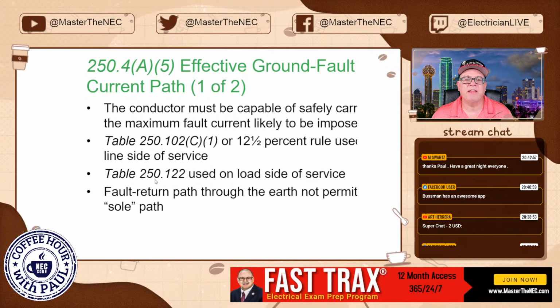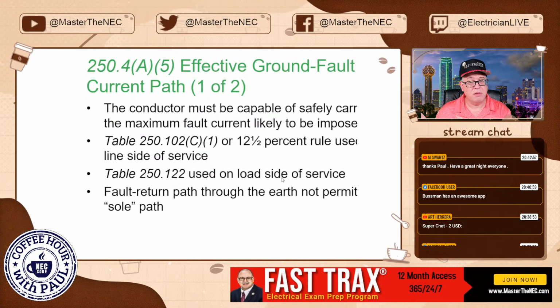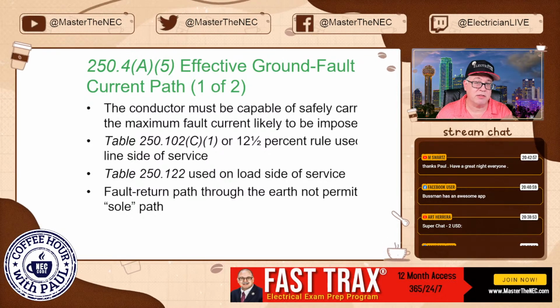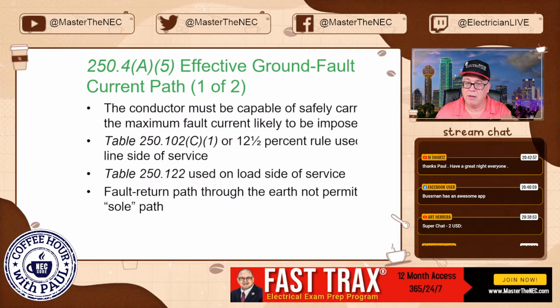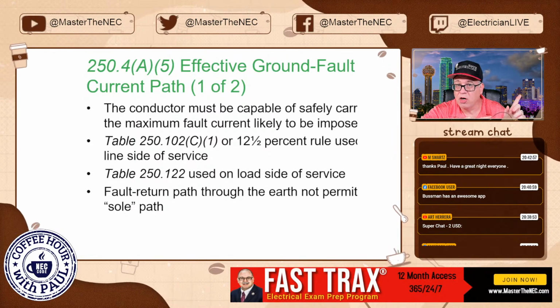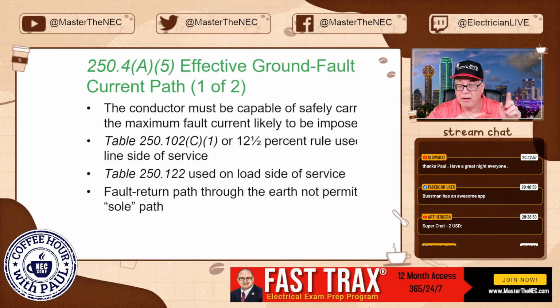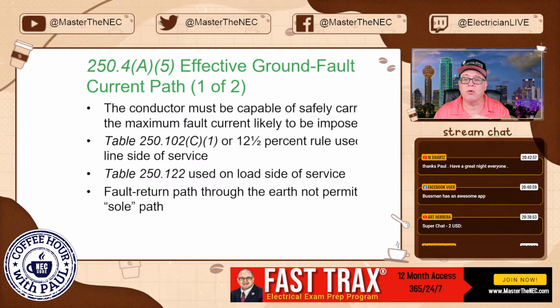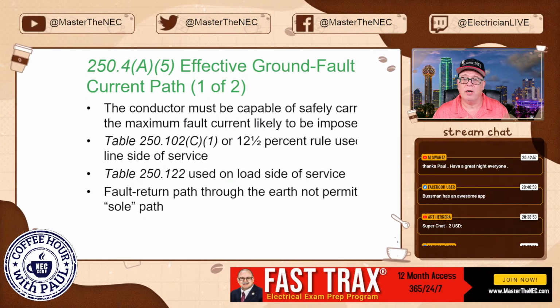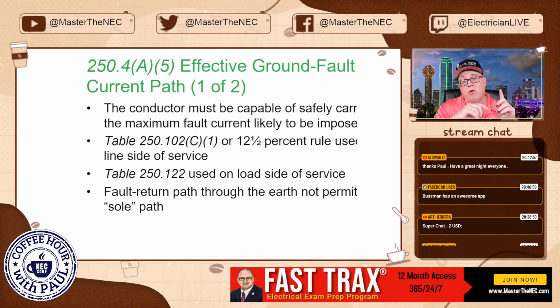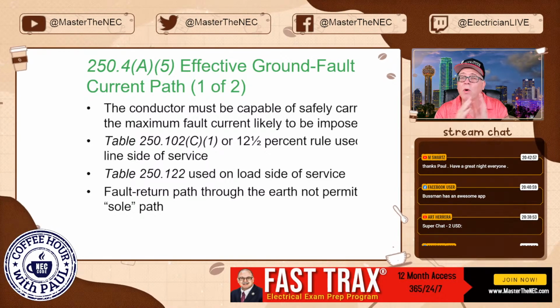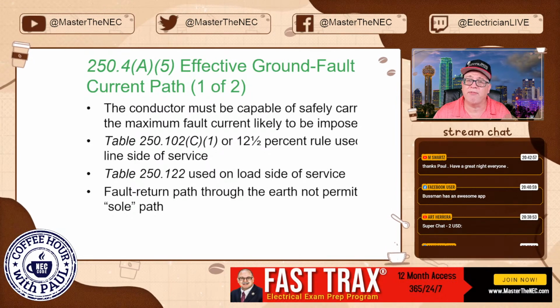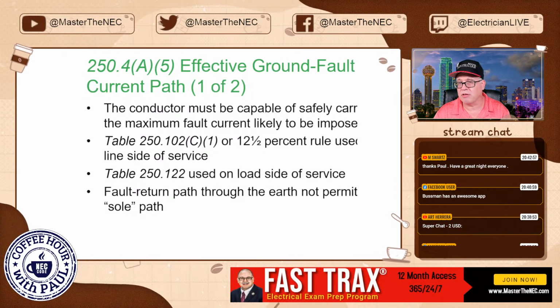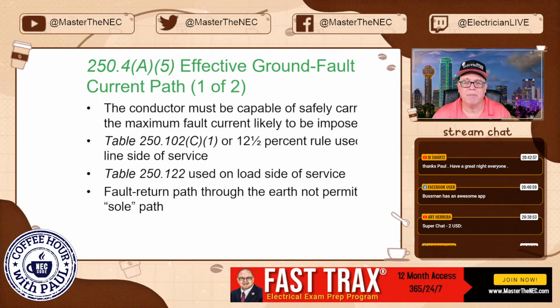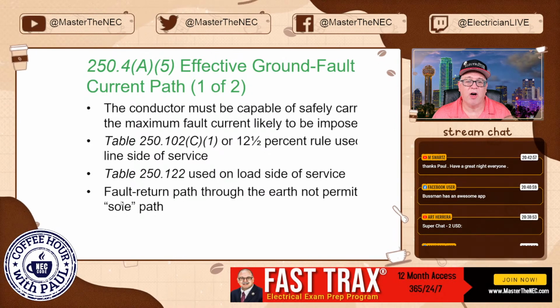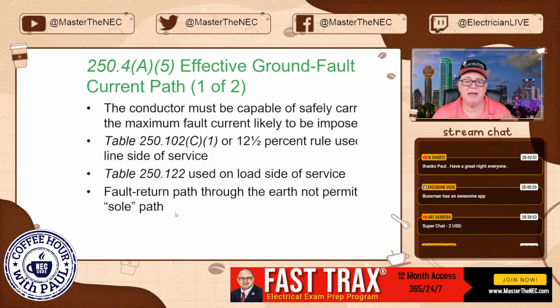Now, table 250.122, that's load side, okay? And that's for things like equipment grounding conductors, and that's based on the size of what? You got it. Size of the overcurrent protective device. Now, the importance here is that whether you're doing supply side bonding jumpers, or you're doing equipment grounding conductors on the load side, whatever you're doing, all of those are still going to be a part of an effective ground fault current path, trying to clear that overcurrent device. Now, a fault current path through the earth is not permitted as the sole path.